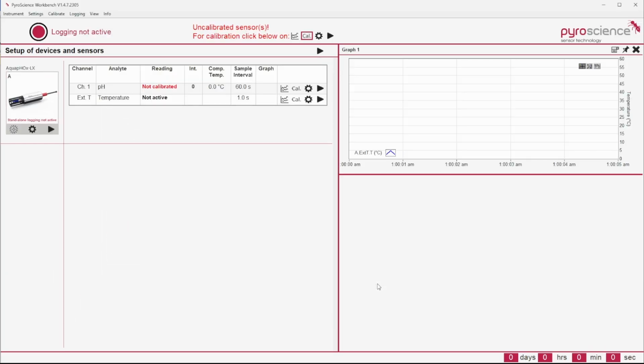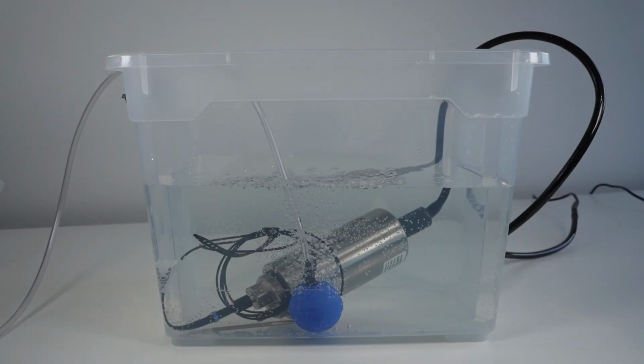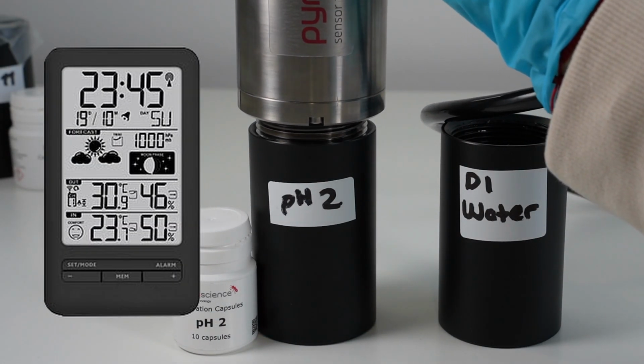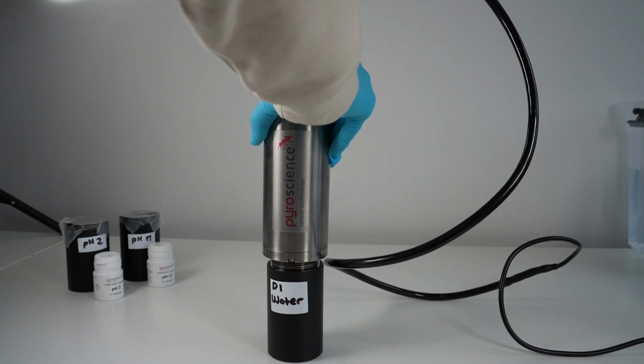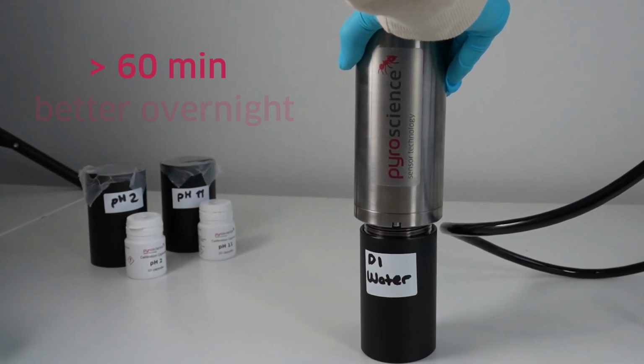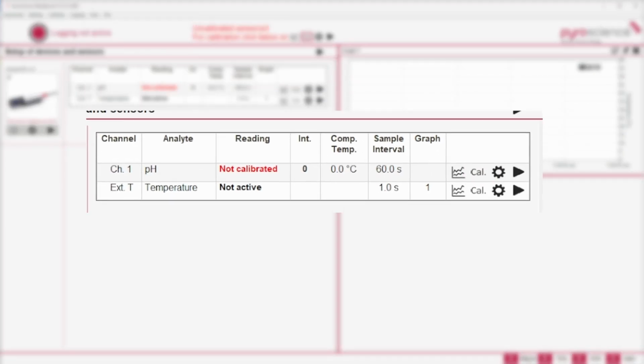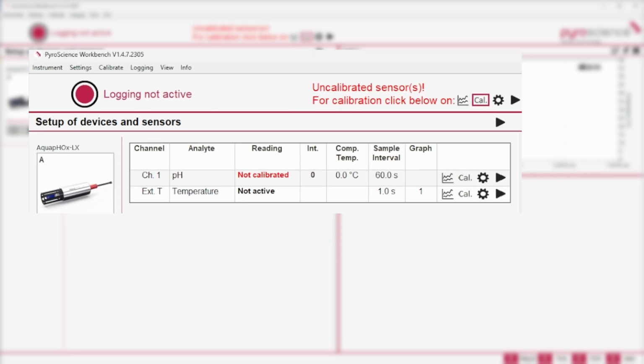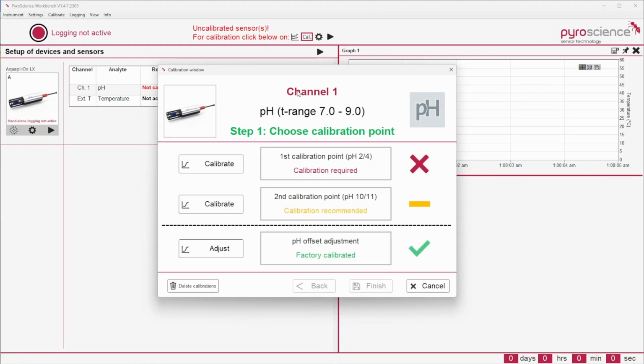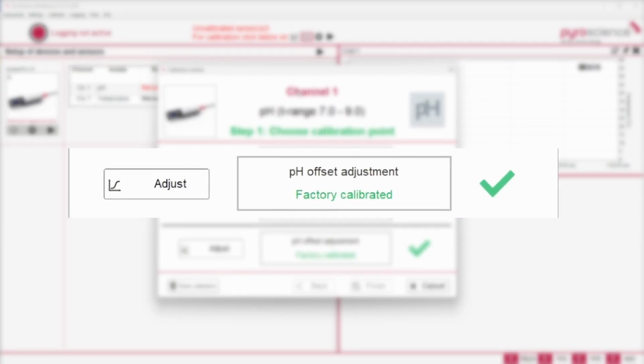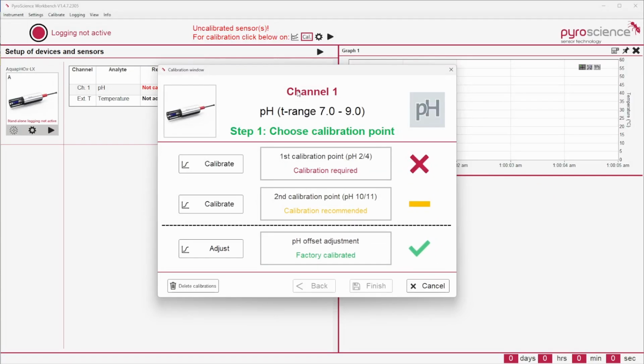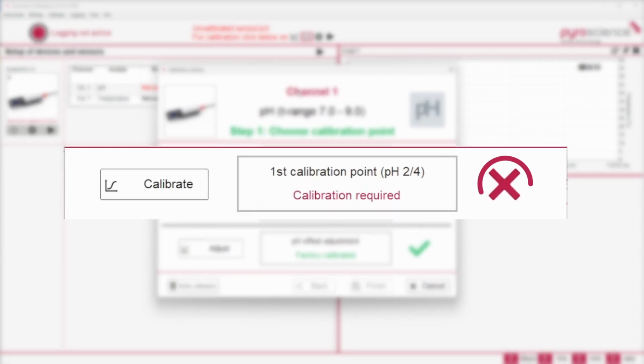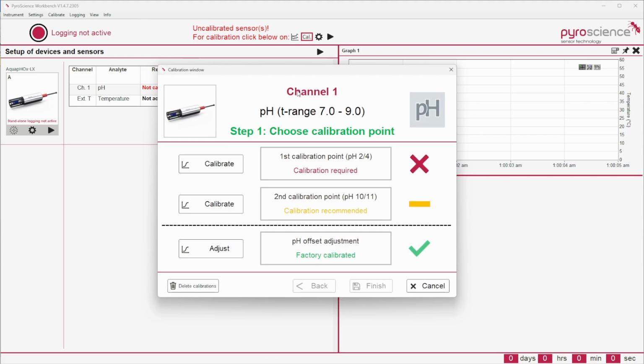After the configuration, the sensors need to be calibrated in freshly prepared calibration standards at constant environmental conditions. Dry pH sensors need to be equilibrated for at least 60 minutes, better overnight, before calibrating or measuring. For calibration, click on Cal on the right side of the configuration overview or use the menu bar at the top of the main window. The new window shows the current calibration state. If the calibration is valid, a green checkmark will be displayed on the right side. If a calibration has to be performed, a red cross will be shown. If a calibration is still valid but shall be refreshed, a yellow bar will appear.